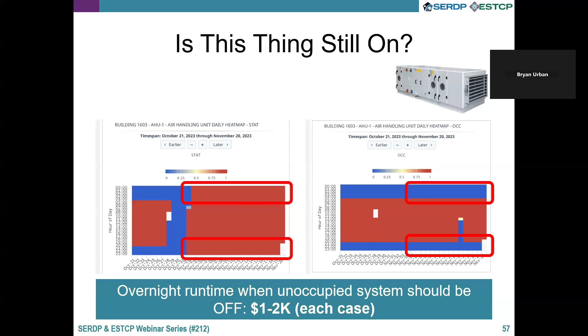But those issues don't get called in as complaints typically because the buildings are comfortable. Nobody's going to notice if it's running overnight and keeping the building on. So these faults could go on for years at a time and waste energy continuously, and they're pretty easy to catch and fix. So for each of these cases, it could be a couple thousand dollars a year in energy savings opportunity, depending on the equipment, how big it is, what fans, et cetera. But those are really, really common and really big opportunities.